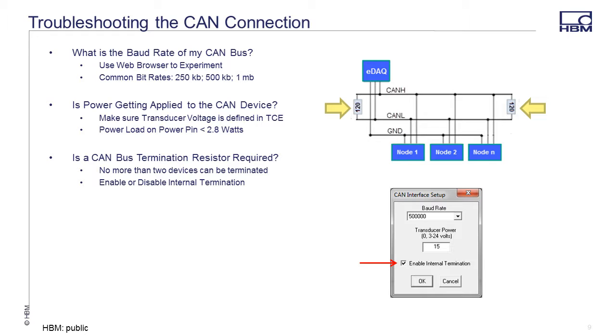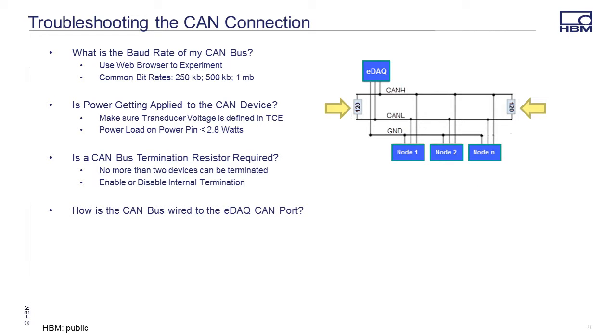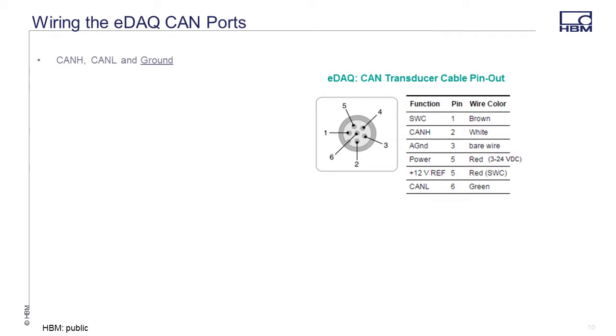That brings us to, how is the CAN bus physically wired to the eDAQ CAN port? With the exception of the CAN port on the legacy high level board, all eDAQ CAN ports use the same wiring scheme. When wiring the eDAQ CAN ports, wire at minimum CAN high, CAN low, and ground to the CAN bus or CAN transducer. The ground wire is important. Leaving the ground wire disconnected between the eDAQ CAN port and CAN controller may result in intermittent CAN operation and data dropouts.